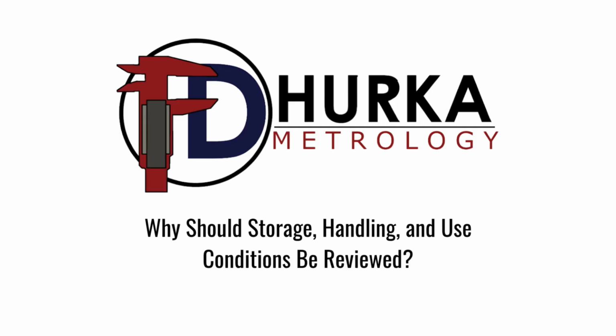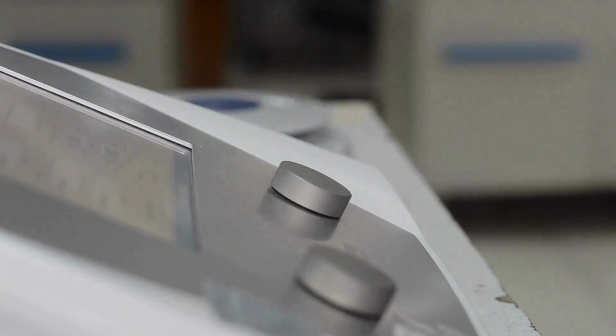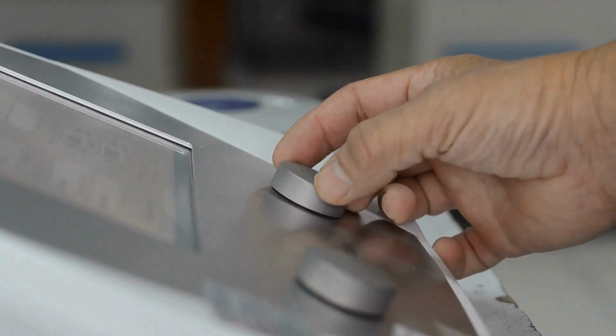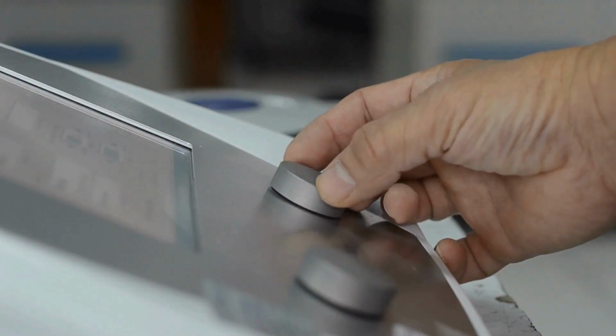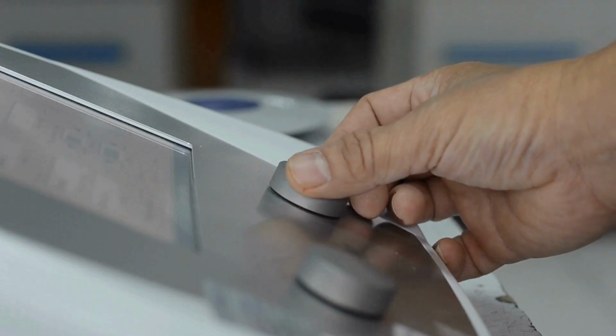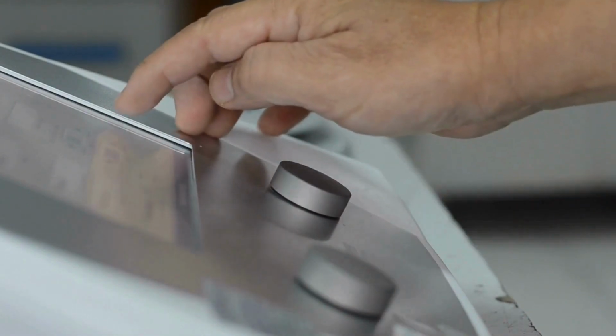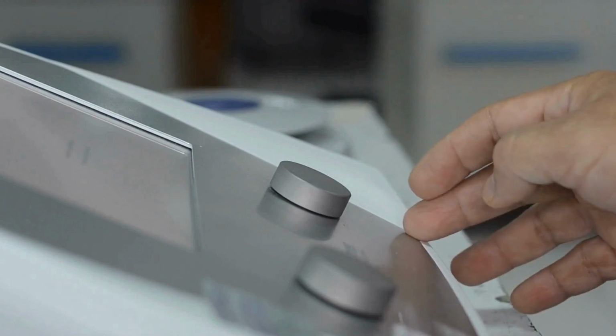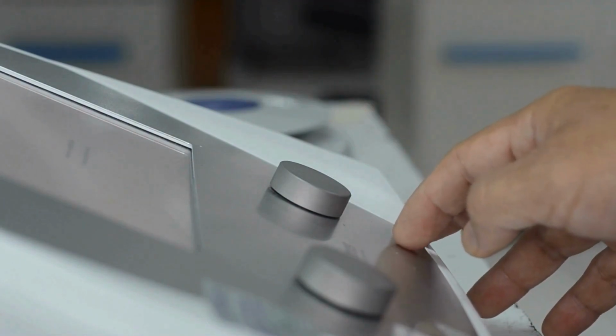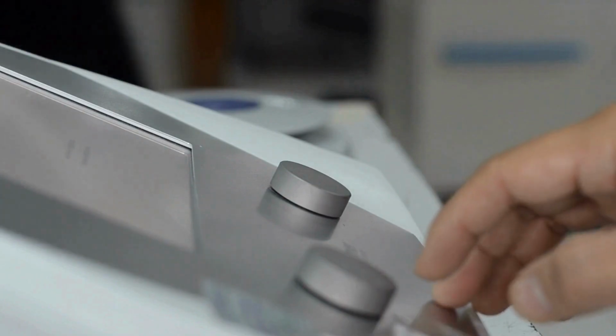Why should storage, handling, and use conditions be reviewed? A failed calibration result may be caused by impact, contamination, temperature extremes, poor storage, excessive wear, or improper use. Identifying those conditions can help prevent the same problem from happening again.